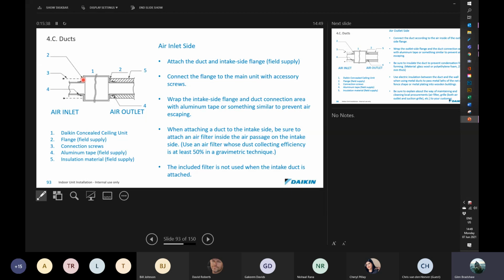Aluminium tape is used just to close up the seals and the edges. Then obviously insulation material, the correct insulation material for the environment in which you're installing. In different areas you can get away with thinner, but it's always important to have a look at what the SANS codes are regarding the insulation materials. So we attach the ducting, intake and side flange. Those are field supply. Connect the flange to the unit, and then we wrap the intake side flange and duct connection areas with aluminium tape or something similar to prevent air escaping.